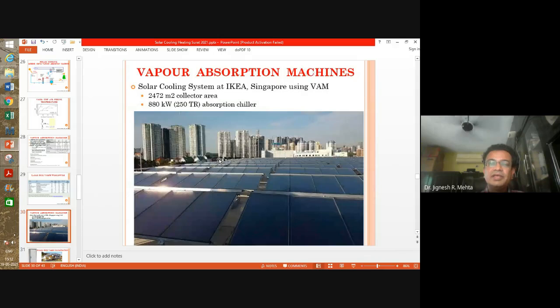Solar cooling system at IKEA Singapore using a vapor absorption refrigeration system. You can see even in such a densely populated city nation, they have been able to put up solar collectors. So this is, you can see, a flat plate collector, and it's using a single effect absorption chiller. Right? So 2472 meter square collector area and 250 tons of refrigeration capacity is put up there.